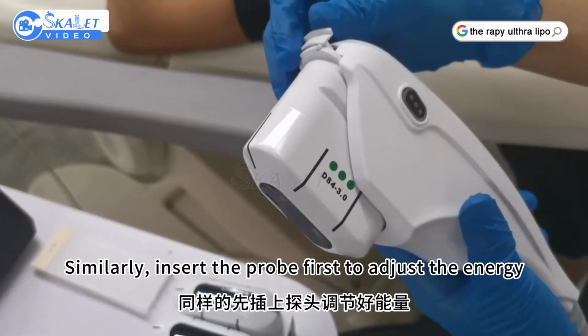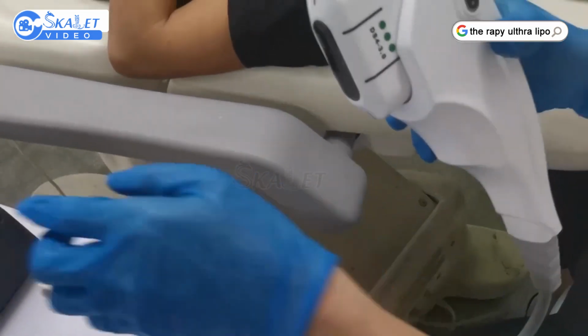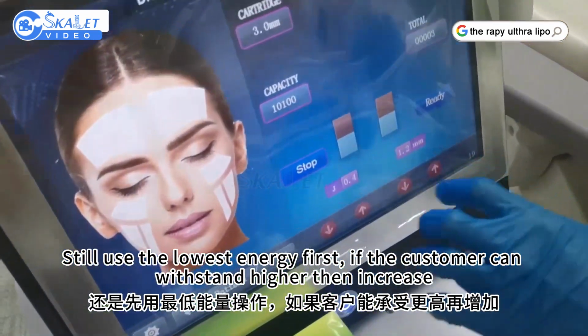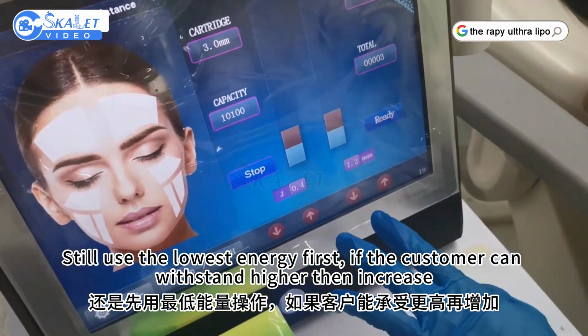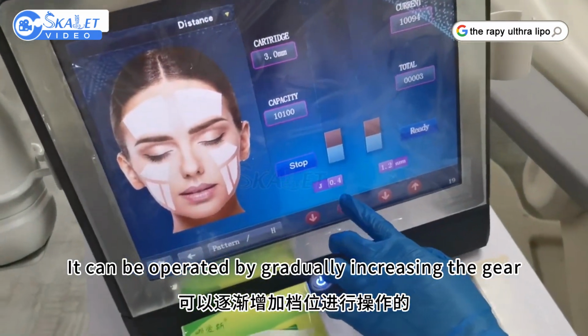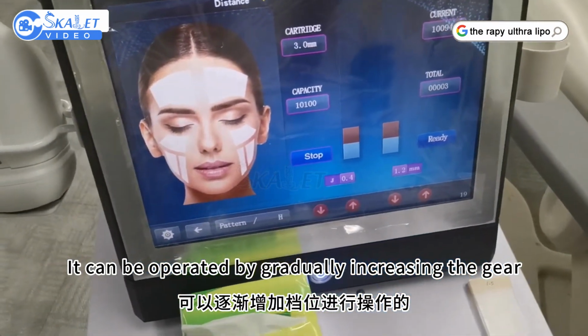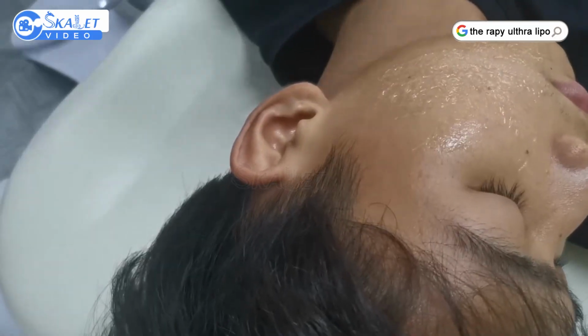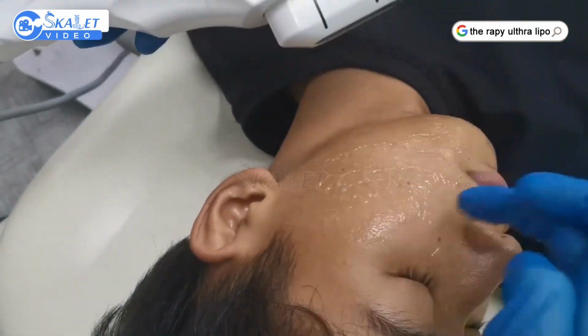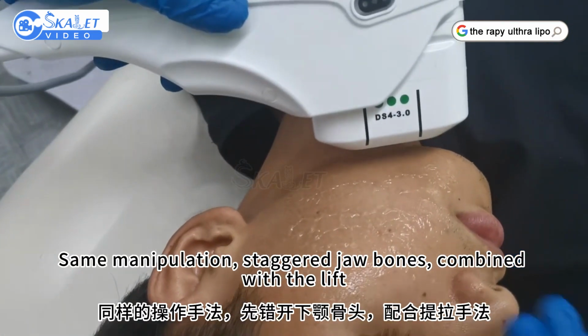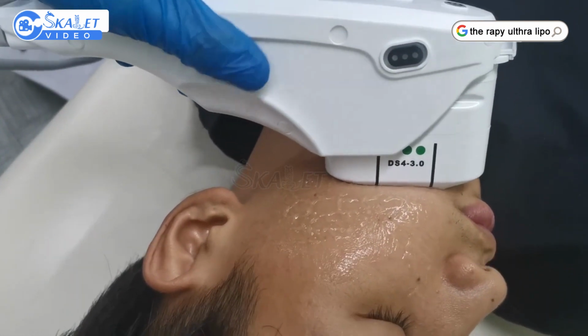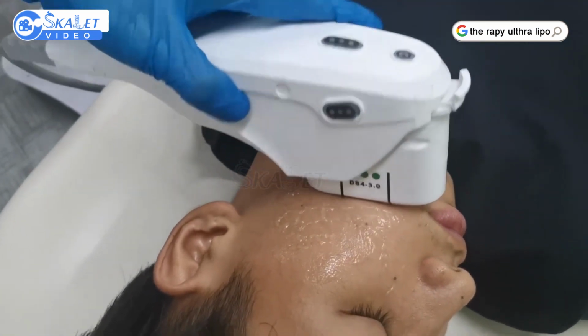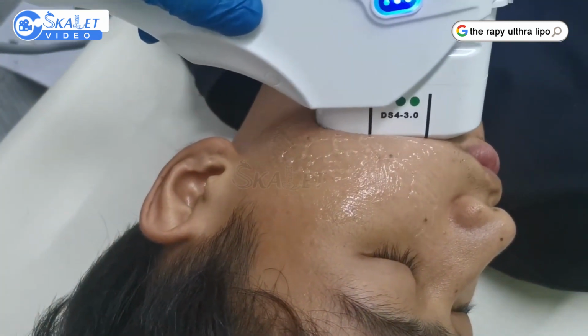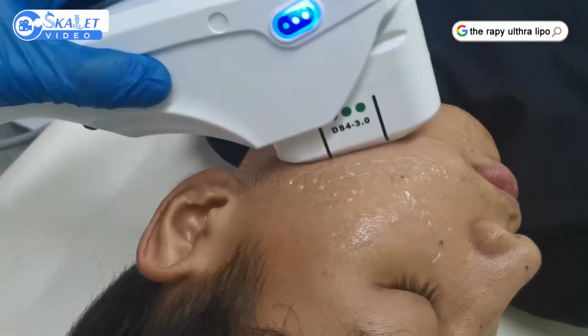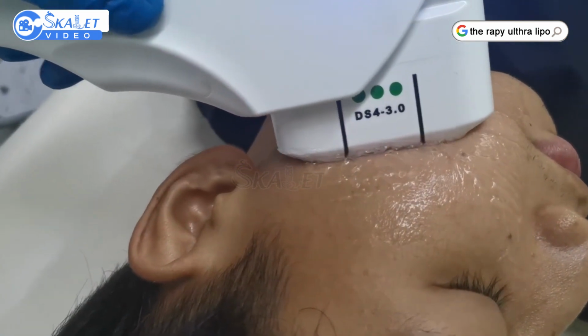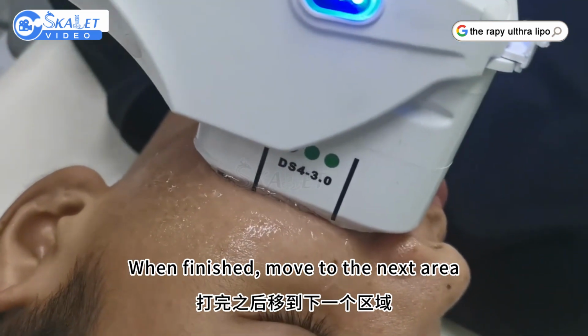Similarly, insert the probe first to adjust the energy. Still use the lowest energy first. If the customer can withstand higher, then increase. It can be operated by gradually increasing the gear. Same manipulation, staggered jaw bones, combined with the lift. When finished, move to the next area.